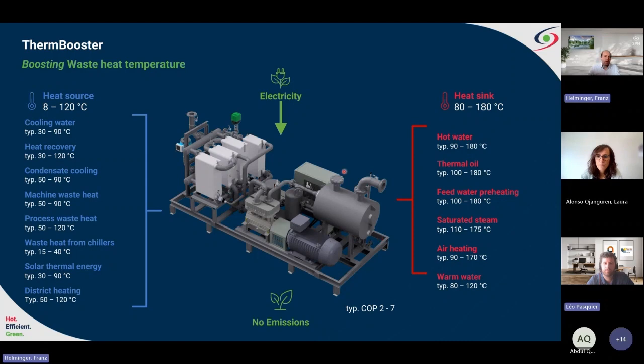It also represents how we name our heat pumps. It's based on the heat transfer fluid of the heat source side and the heat sink side, and then the number of compressors. In this case, we have an LS1, which means liquid at the heat source, steam at the heat sink, and 1 compressor. We manufacture up to 3 compressors on 1 heat pump frame. The higher the temperature lift from heat source to heat sink, the lower the COP, but with very low temperature lift, we have experience with COPs up to 7.